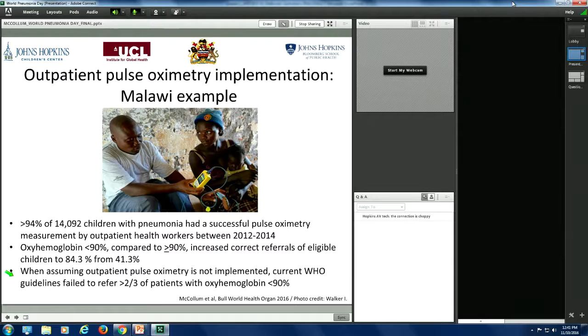So what are the gaps with pulse oximetry? How come it hasn't been implemented more widely at these lower health system levels? Well, more health outcome data is needed in settings other than Malawi. Pulse oximetry devices appropriate for children remain too expensive. The price point for quality devices that provide accurate measurements is more than $200 to $250 per unit in US currency. There are also no adequate reusable probes for children 0 to 5 years of age within a reasonable price range. What I mean by that are probes that are accurate, robust and durable, and that fit children well.